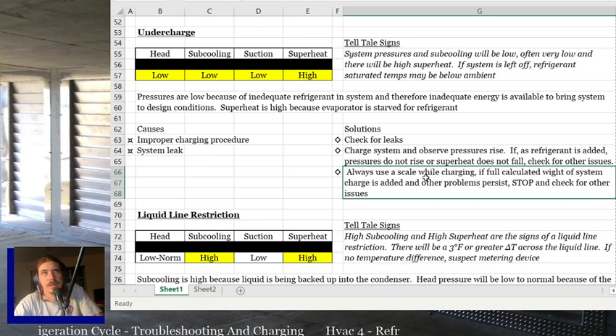I think next Tuesday will probably be the class where we cover TXVs, if I had to guess. But just remember, for all these charts, TXVs may help skew it to normal if it affects the suction side of the system. If it doesn't affect superheat or suction pressure, then it won't matter that you have a TXV. But if it does affect that side of the system, it may skew towards normal, and it may not be quite as obvious that the suction pressure is low and the superheat's high.